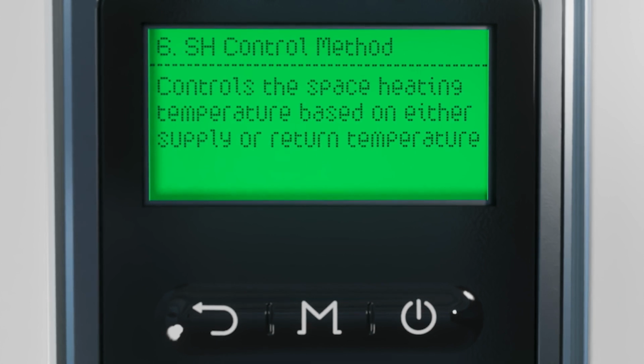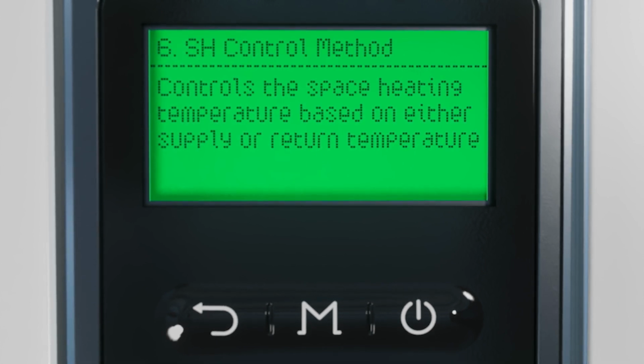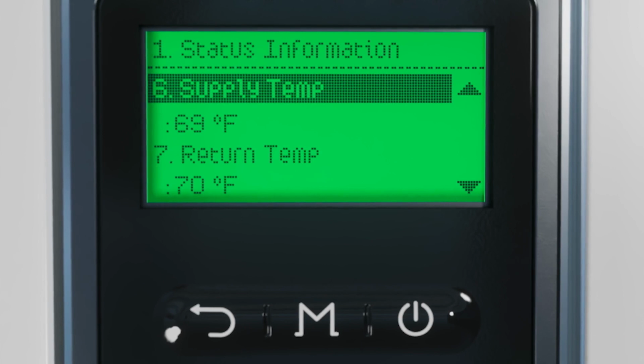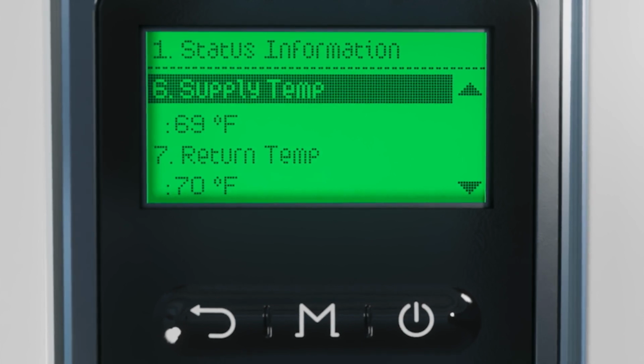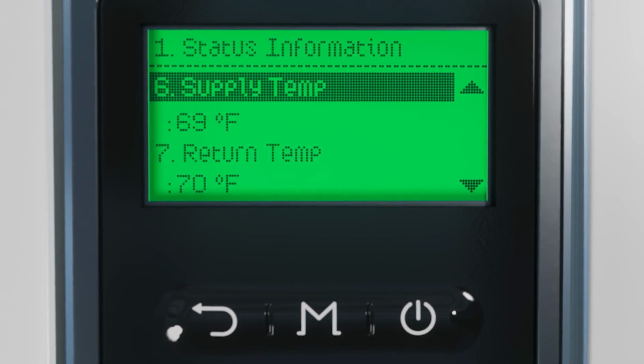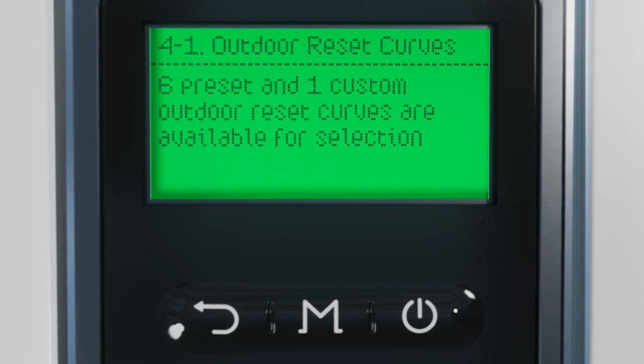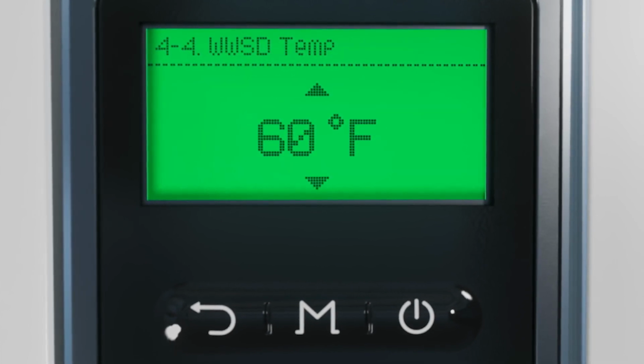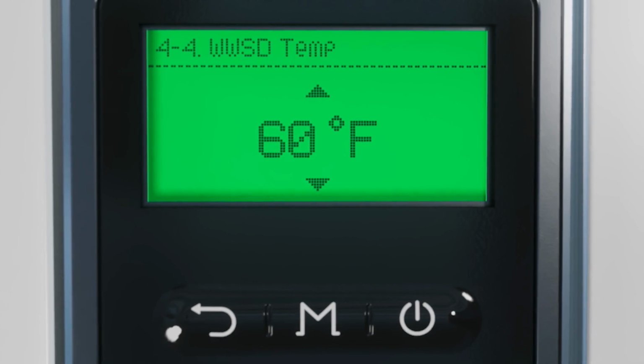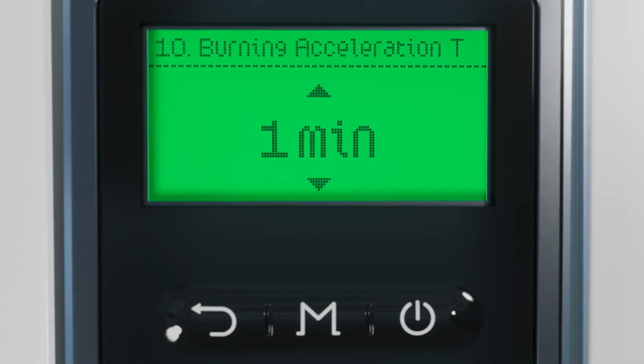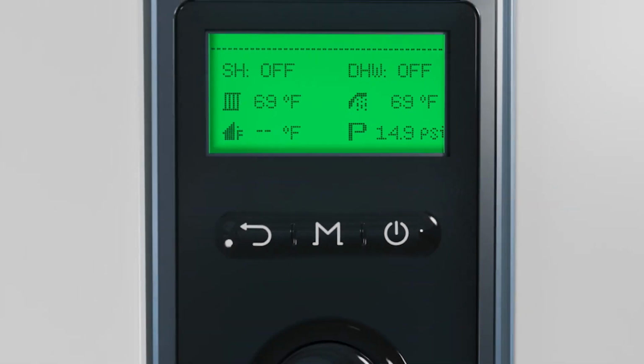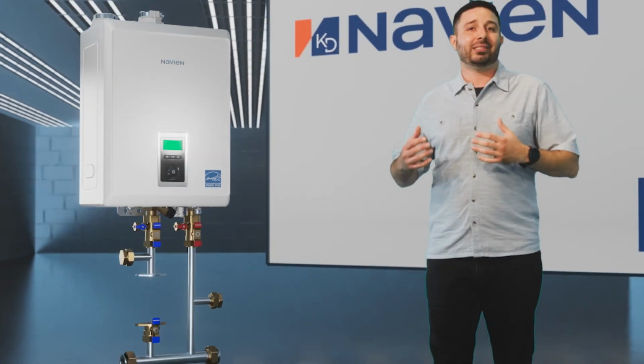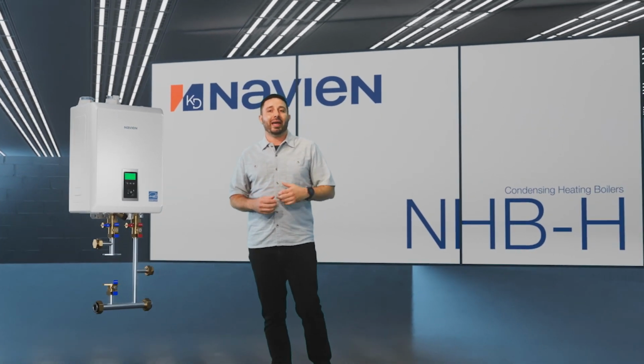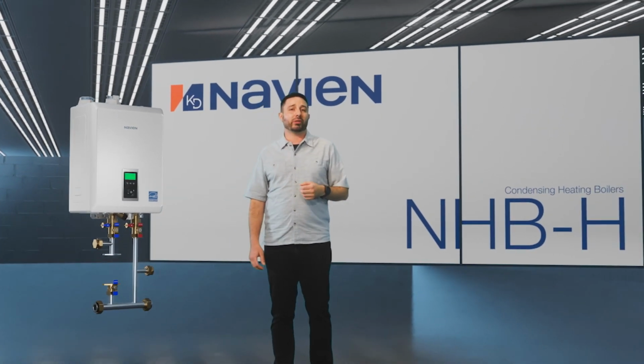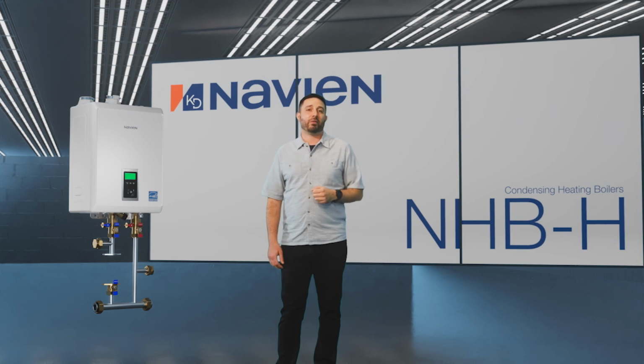And we give you more control over the heating process than ever before with features such as the ability to control the supply or return water temperature, programmable outdoor sensor values with a boost capability, multi-temperature zoning, and adjusting both the maximum capacity and burner acceleration timing based on specific heating requirements. This new introduction builds on existing strengths of the Navien product line and delivers a premium condensing boiler experience that you can only get from Navien.